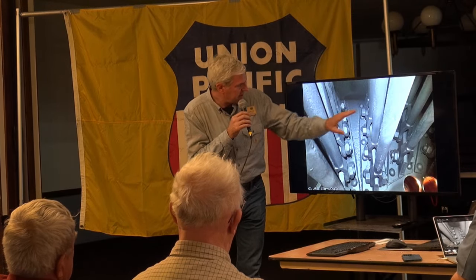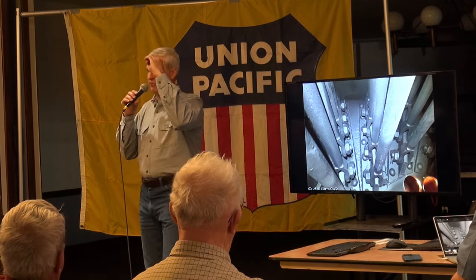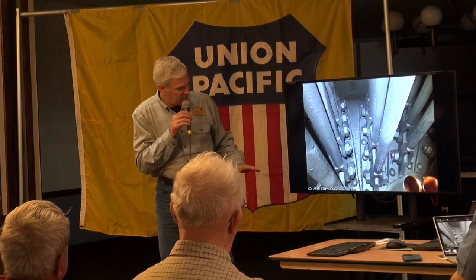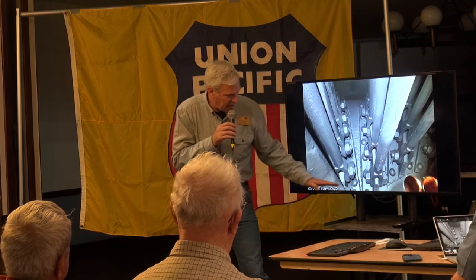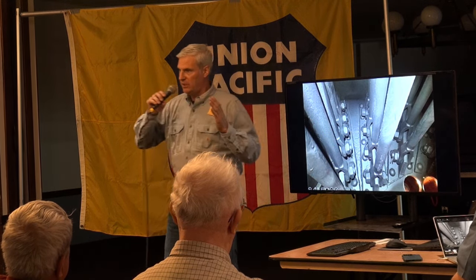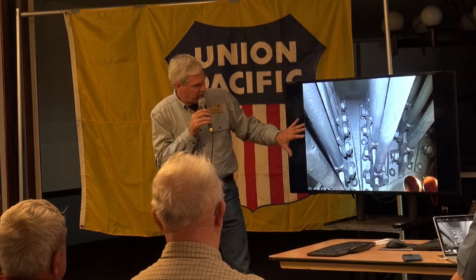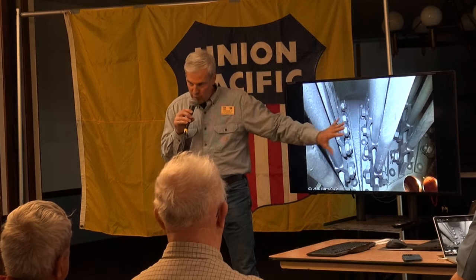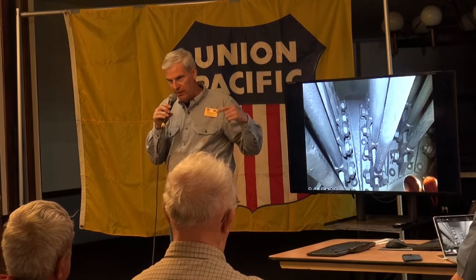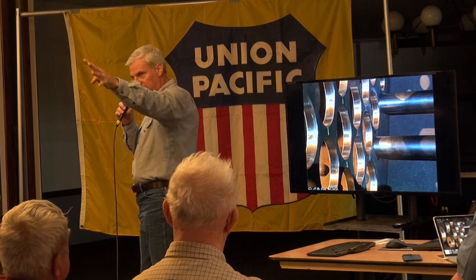All of these giant braces, you can't quite see them the way the picture is taken here, but these are giant forged rods of varying lengths, and they all attach to what we call the unstayed surface. So any of this stuff here, above the area, the tubes themselves are attached in a way that holds one tube sheet and the other one together. Those are stayed, so that's a stayed surface. This area here, had it not been for these, would be unsupported, and there's no way it could withstand the pressure. So all of these structures here, when you're laying in there, they're all varying lengths. And some of them go all the way back to the dome. And they're all in a nice symmetrical radial pattern.